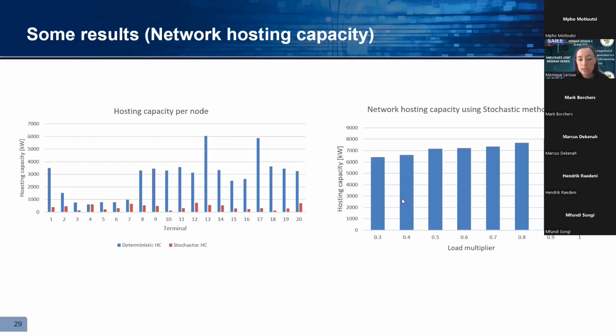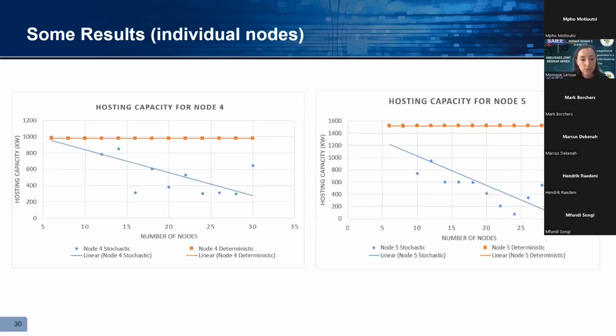Let me just quickly go through this. It also just shows here that as you increase your load in your system, your hosting capacity will increase. So if your load is at 30% of its normal loading, your hosting capacity obviously would be a lot less than when your load is at 100%, which also just highlights to users that they need to consider the worst case scenario, which is low load, because that would give you the true hosting capacity, compared to if you had full load. Your hosting capacity will be a lot more, but that's not reflective of what can be expected on the network.